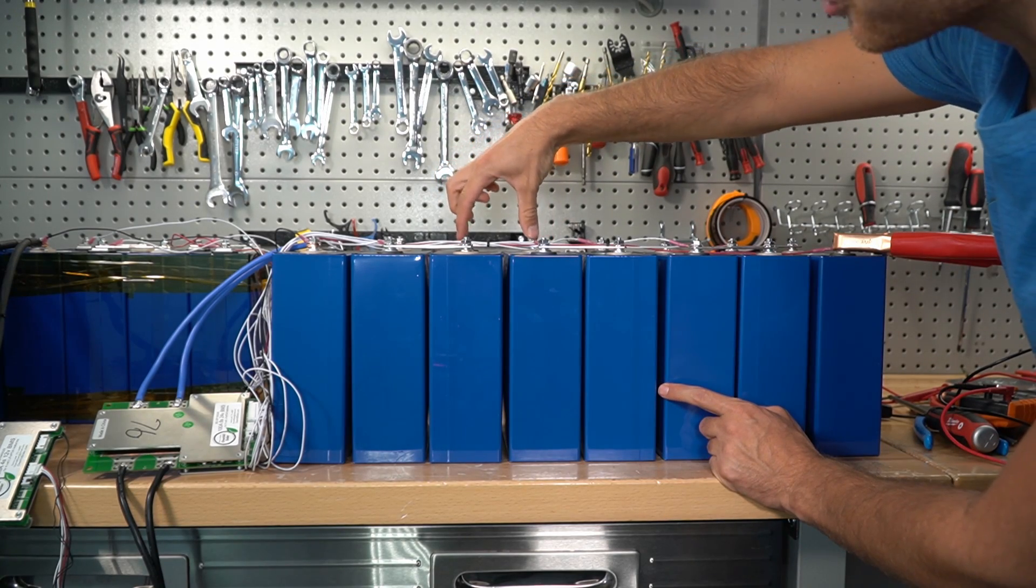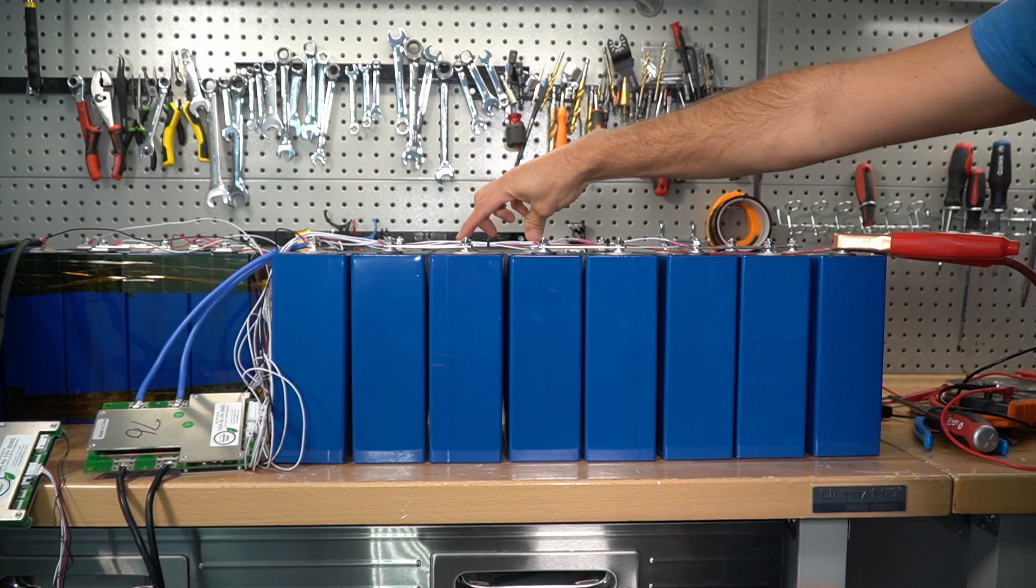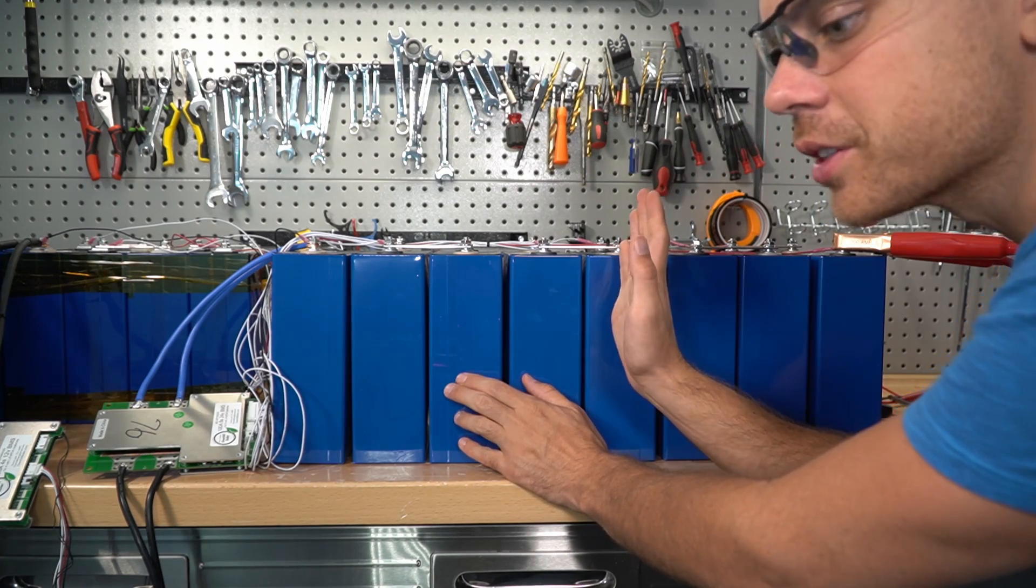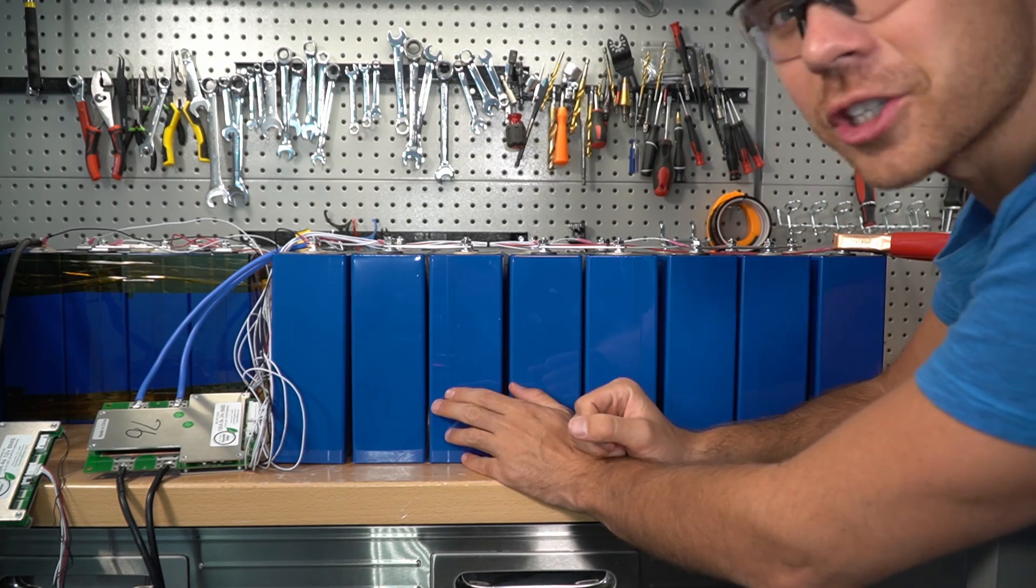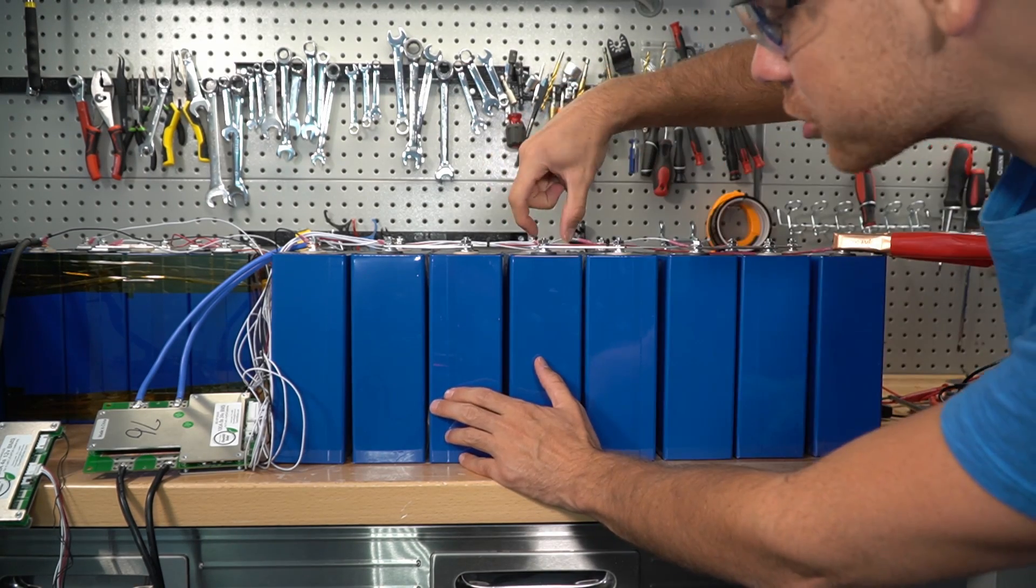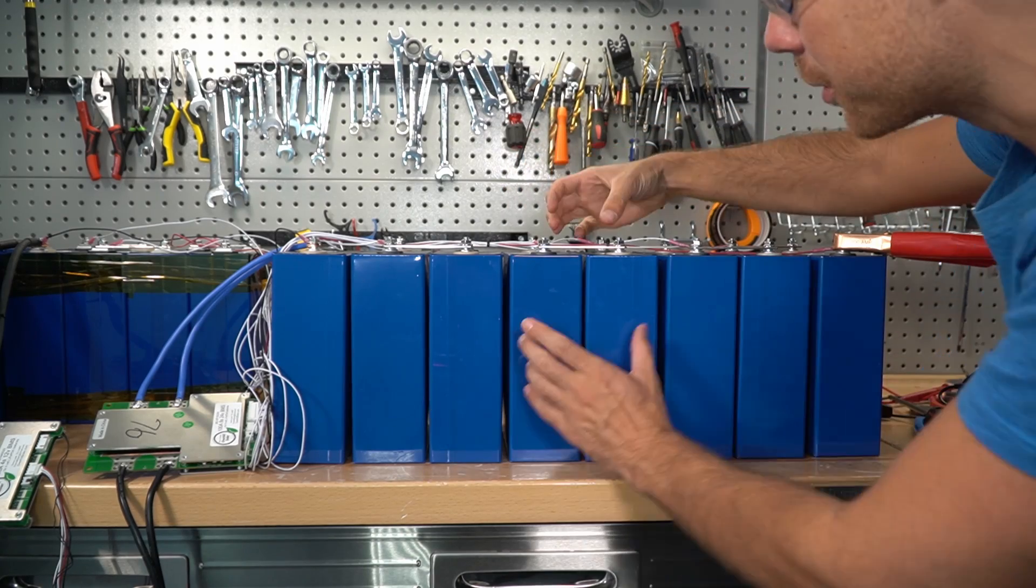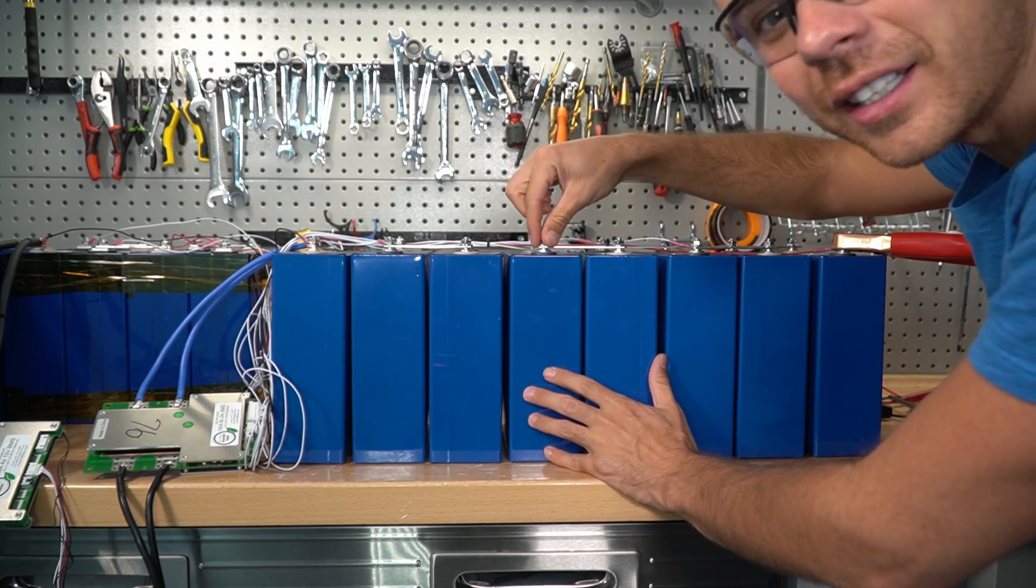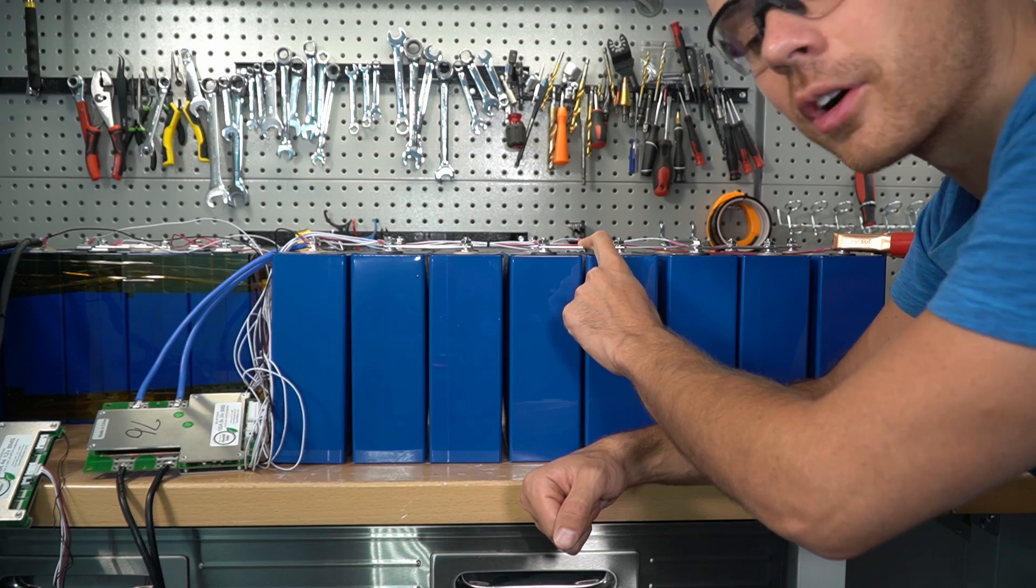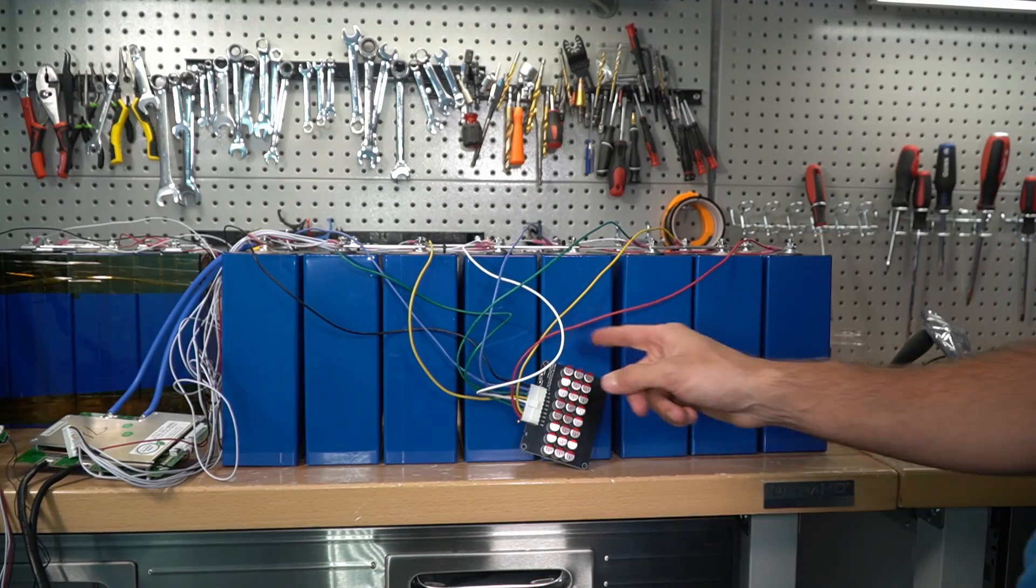So that means there's stress on these terminals over here. I always thought about the lateral forces on the terminal, but with this much expansion and contraction, we're actually getting a rotation on these terminals, because they're spreading apart, and it's rotating. And obviously having flexible bus bars would be great in this situation.